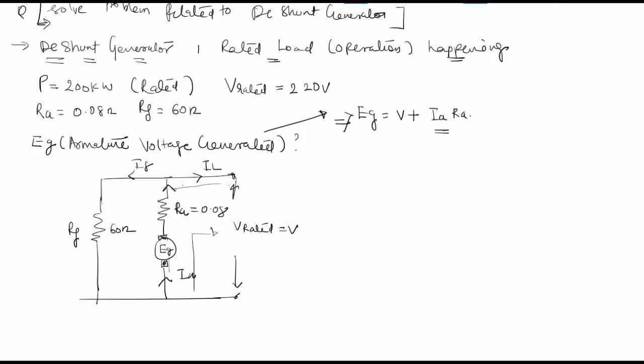The load current IL is found from the rated power divided by the rated voltage: IL equals 200 times 10 to the power 3 divided by 220, which equals 909.09 amperes.